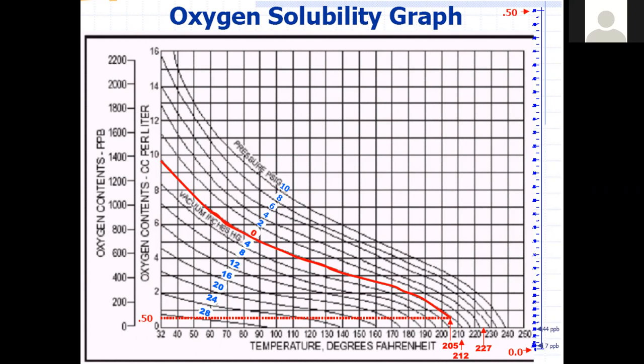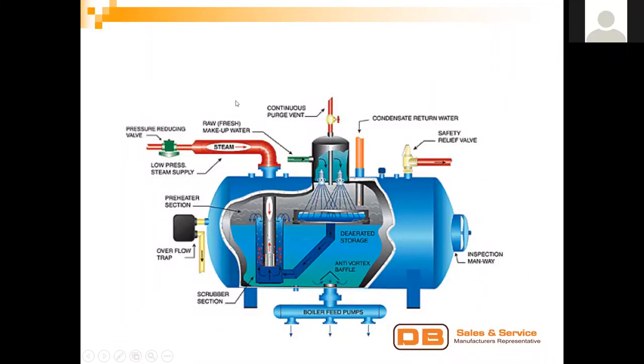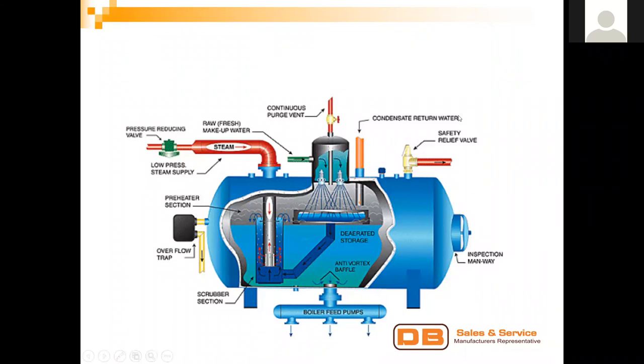How does a deaerator work? It takes live chest steam and fresh makeup water. A spray type deaerator runs water through atomizing nozzles, atomizing it into tiny droplets and running it over a chest of steam. As those water droplets approach the steaming temperature, most of the oxygen is driven out of solution and exits through a continuous purge vent at the top. The de-aerated water then flows down to the boiler feed water header, through the feed water pumps, and is pumped to the boiler with the majority of oxygen removed. Any residual oxygen is then addressed with an oxygen scavenging chemical downstream of the pumps.